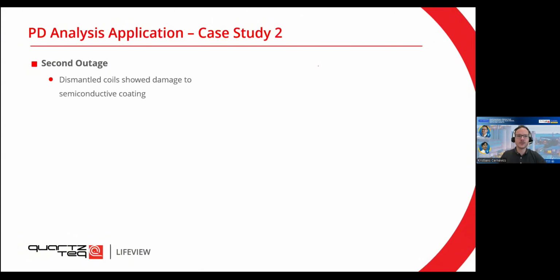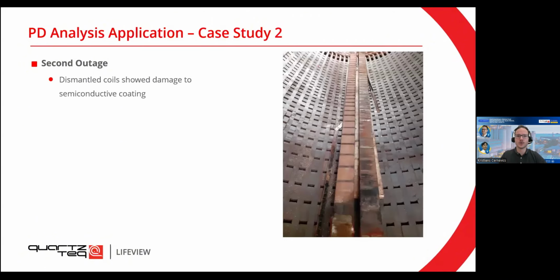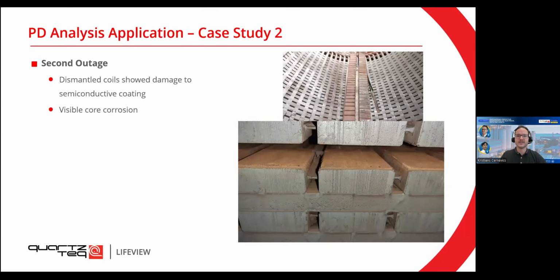So in the second outage, they dismantled the coils, which showed serious damage to the semiconductive coating and visible core corrosion. And a full rewind was recommended and undertaken. And fortunately, in this case, we managed to install this condition monitoring device, and we managed to prevent catastrophic failure.